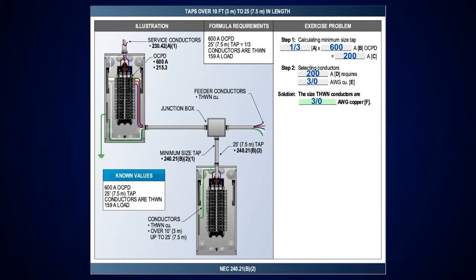We're in 240.21(B)(2). I said everything else we take at a third. So I take 600 amps at a third. That's going to give me 200 amps. Once again, I go to table 310.16, 75 degree C column. Come down. You're going to pick up the next value equal to that. In this case, it's 200 amps. Come across the left-hand side, it's going to tell you it's a 3-aught conductor. So your size THWN copper conductors for this tap will be 3-aught.